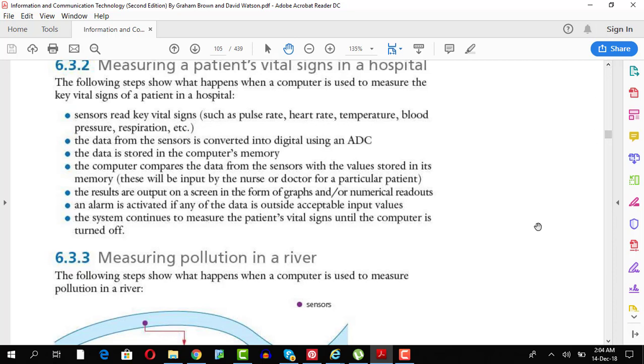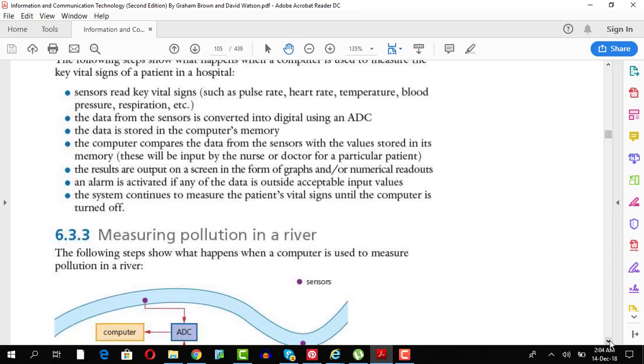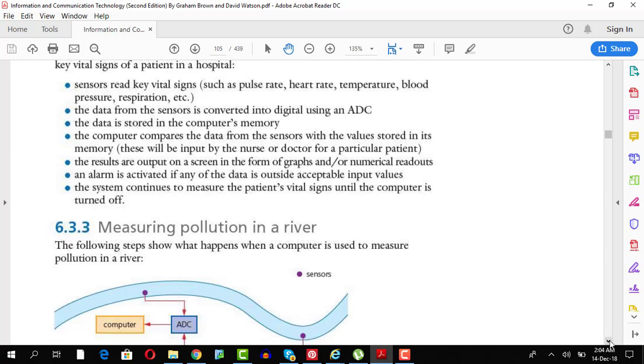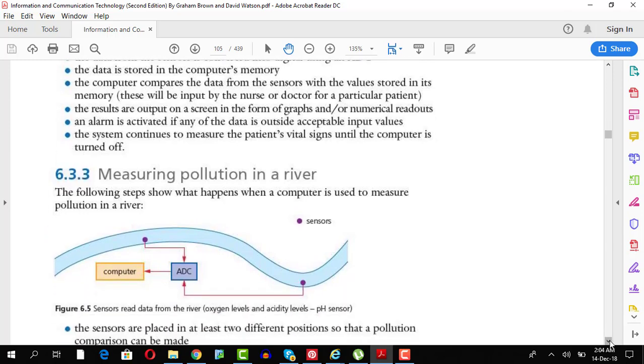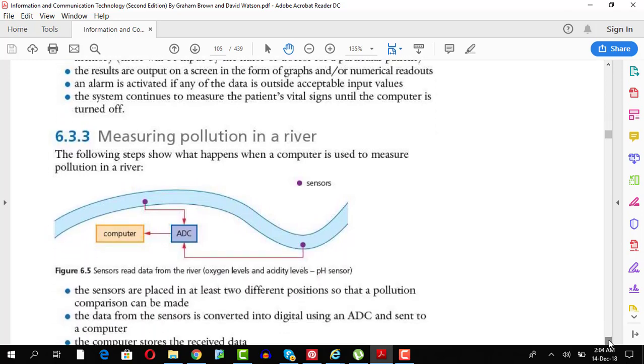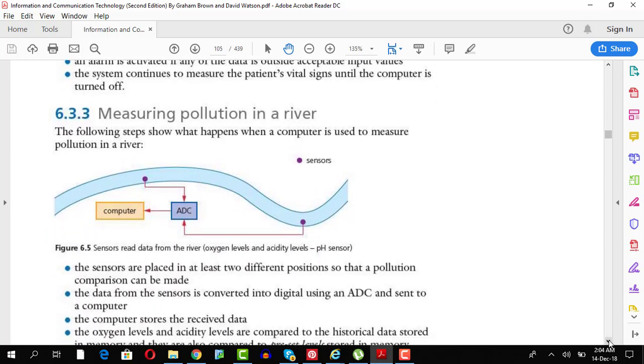So, if you set a value, let's say 100 and if it goes beyond 100, it will trigger an alarm telling you that it has crossed the limit. Sensors take the data from the environment and tells that whether the actual data in the environment has crossed the preset value. So, you have one value is changed and one value is not changed. Preset value and actual value. For example, in your air condition system, you have two values. Preset value and actual value. Your room right now is at 25 degrees Celsius, but you want it to come down to 18 degrees Celsius.